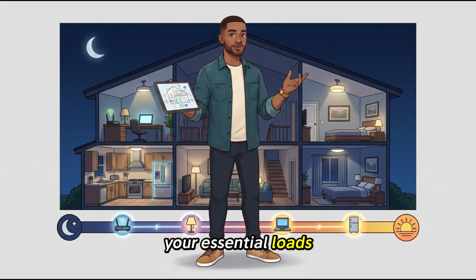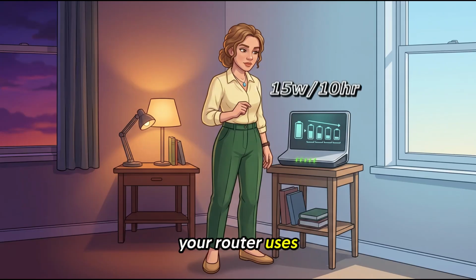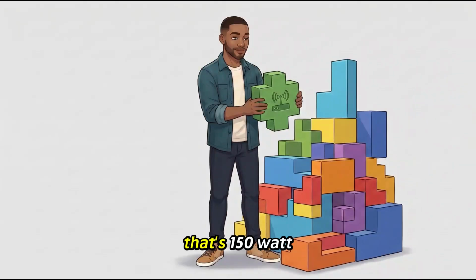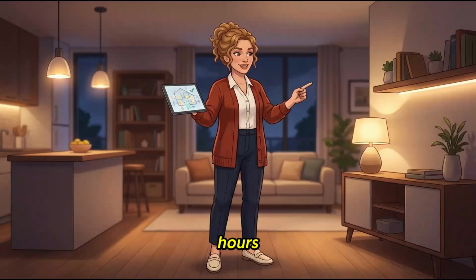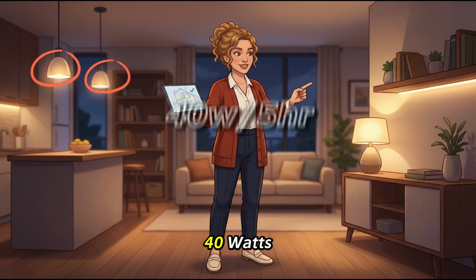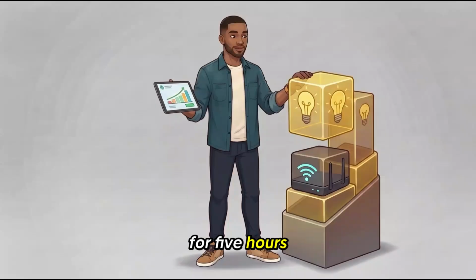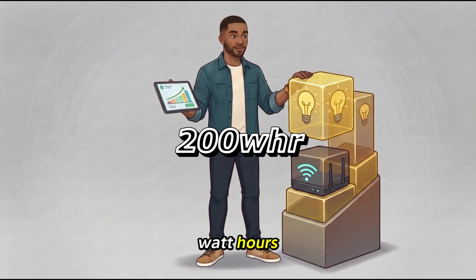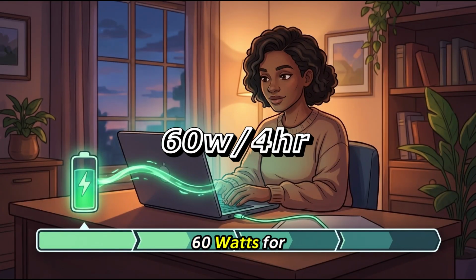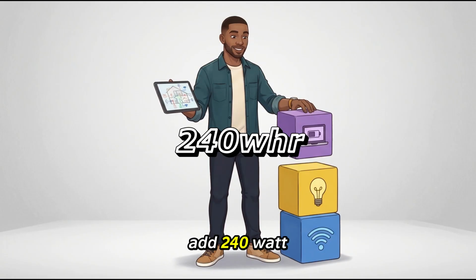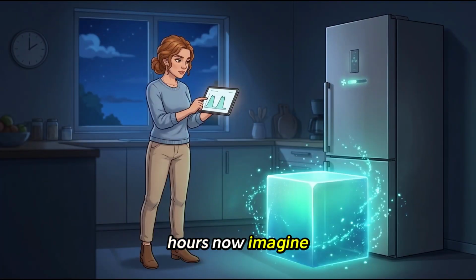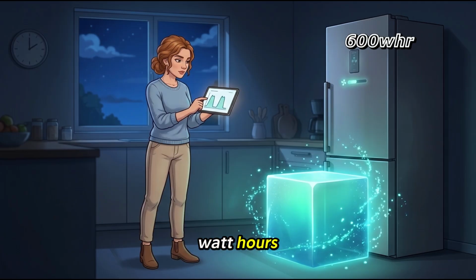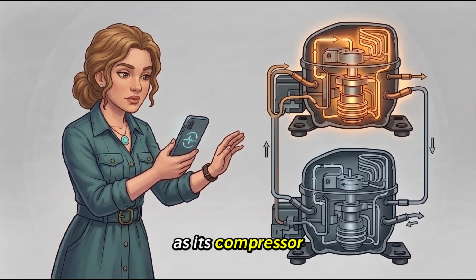Imagine your essential loads require the following energy during a 10-hour outage. Your router uses 15 watts for 10 hours, that's 150 watt-hours. Four efficient lights use a combined 40 watts for 5 hours, that's another 200 watt-hours. Your laptop averages 60 watts for 4 hours, add 240 watt-hours. Now imagine your refrigerator consumes an estimated 600 watt-hours across the night as its compressor cycles on and off.